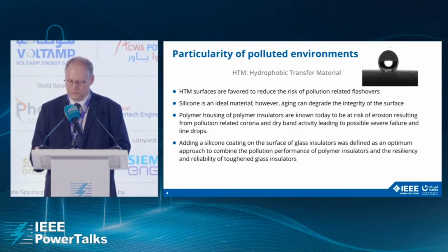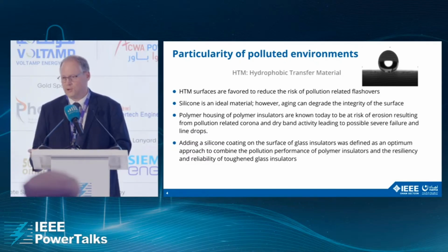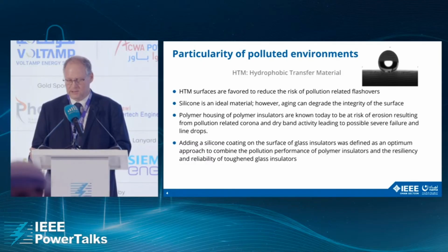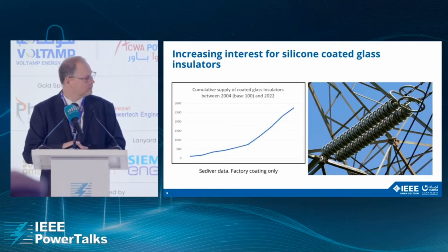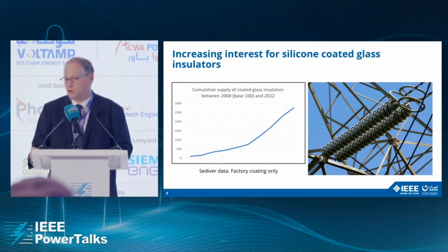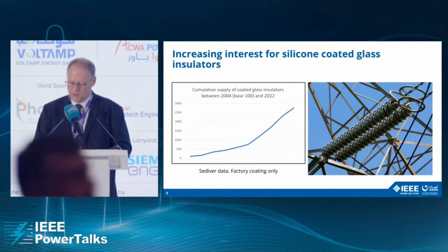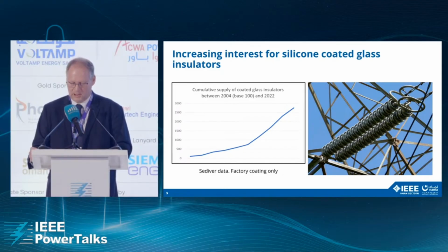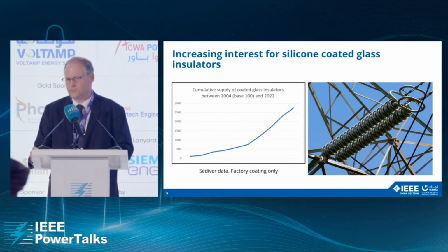Adding a silicone coating on the surface of a glass insulator was defined as the optimum approach to combine the pollution performance of polymer insulator and the resiliency and reliability of toughened glass insulators. RTV coating on glass and porcelain insulators is no longer considered as a marginal approach, but is clearly part of the design of new transmission lines, especially in this region of the world. The major push came from the decision taken more than 20 years ago to have a product coated in a factory with an industrial process in controlled conditions rather than in the field, where the difficulty of uncontrolled outdoor conditions can compromise the long-term performance of the product.